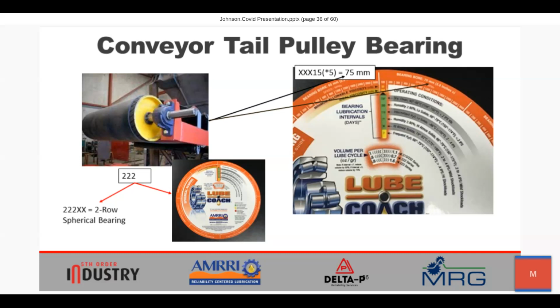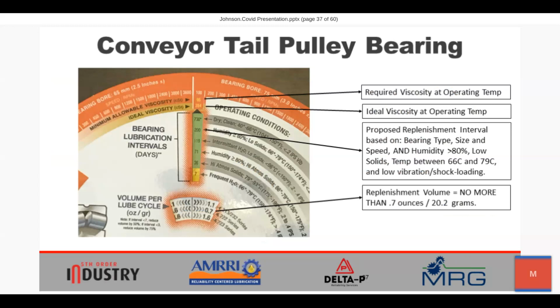So that would be the orange calculator. The first 3 digits designate the bearing type and gauge. The last 2 digits, once again, when multiplied by 5, give us the bore dimension for this bearing. So 222-15 is a 75 millimeter bore. We turn our dial indicator to the location that gives us 75 millimeters.